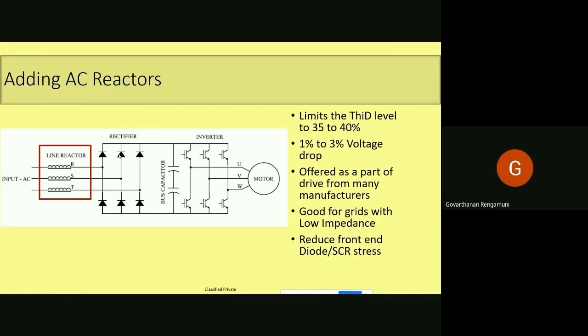The second mitigation technique is adding an AC reactor. Here we are not using a DC reactor, but an AC reactor is added. By doing this, we can get similar limits of 35 to 40%, but there will be a considerable voltage drop. As I already mentioned, these inductors will face only AC current, so the drop can vary from 1% to 3%. Many drive manufacturers offer this as a part of the drive, because it gives one more advantage. If there are grid disturbances, it can protect the diode rectifier from them. So instead of having the line reactor on the DC side, the other preference could be on the AC side. This is good for grids with low impedance. So this is the second technique.